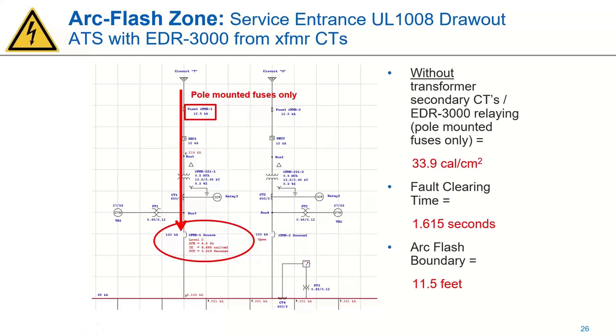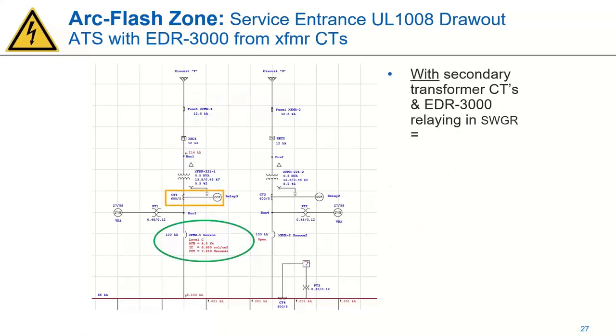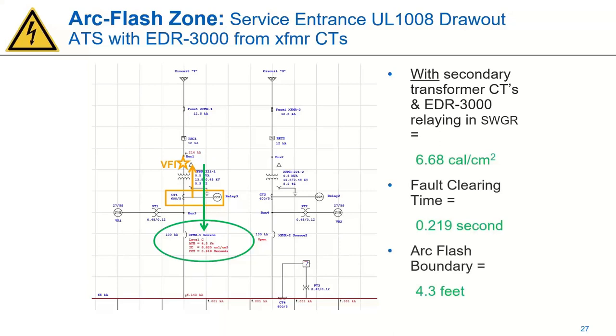So we'll look at that again, now utilizing those secondary CTs to trip that VFI. So sense that secondary overcurrent. Again, our secondary relaying does not have to be coordinated for inrush. That's going to trip it quite a bit faster. That's going to get us down below that 8 level. And again, this isn't always on. This is not a maintenance mode. This isn't something that's upgraded in any way manually. This is something that's always going to give you that level of arc flash protection.